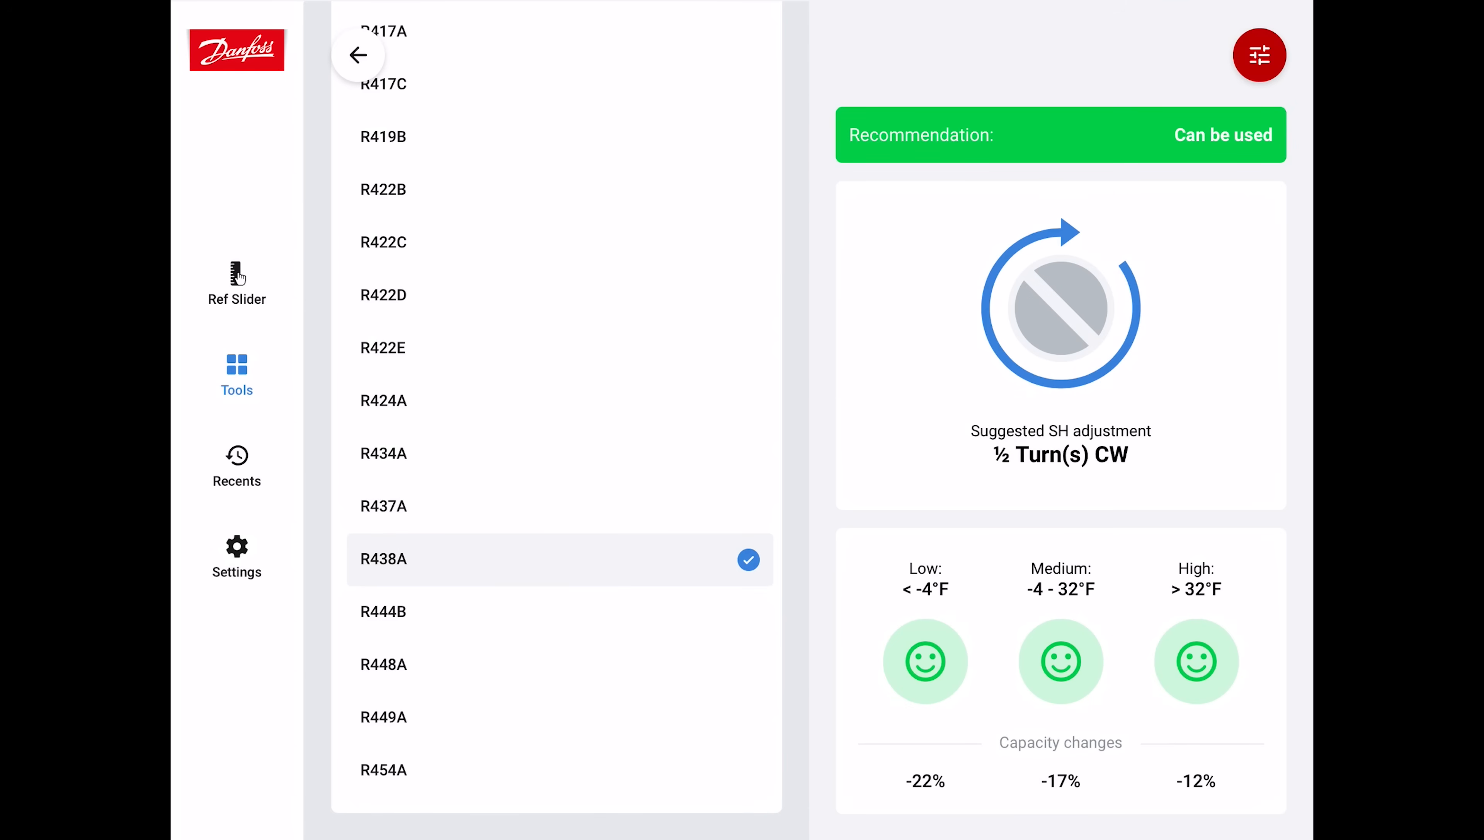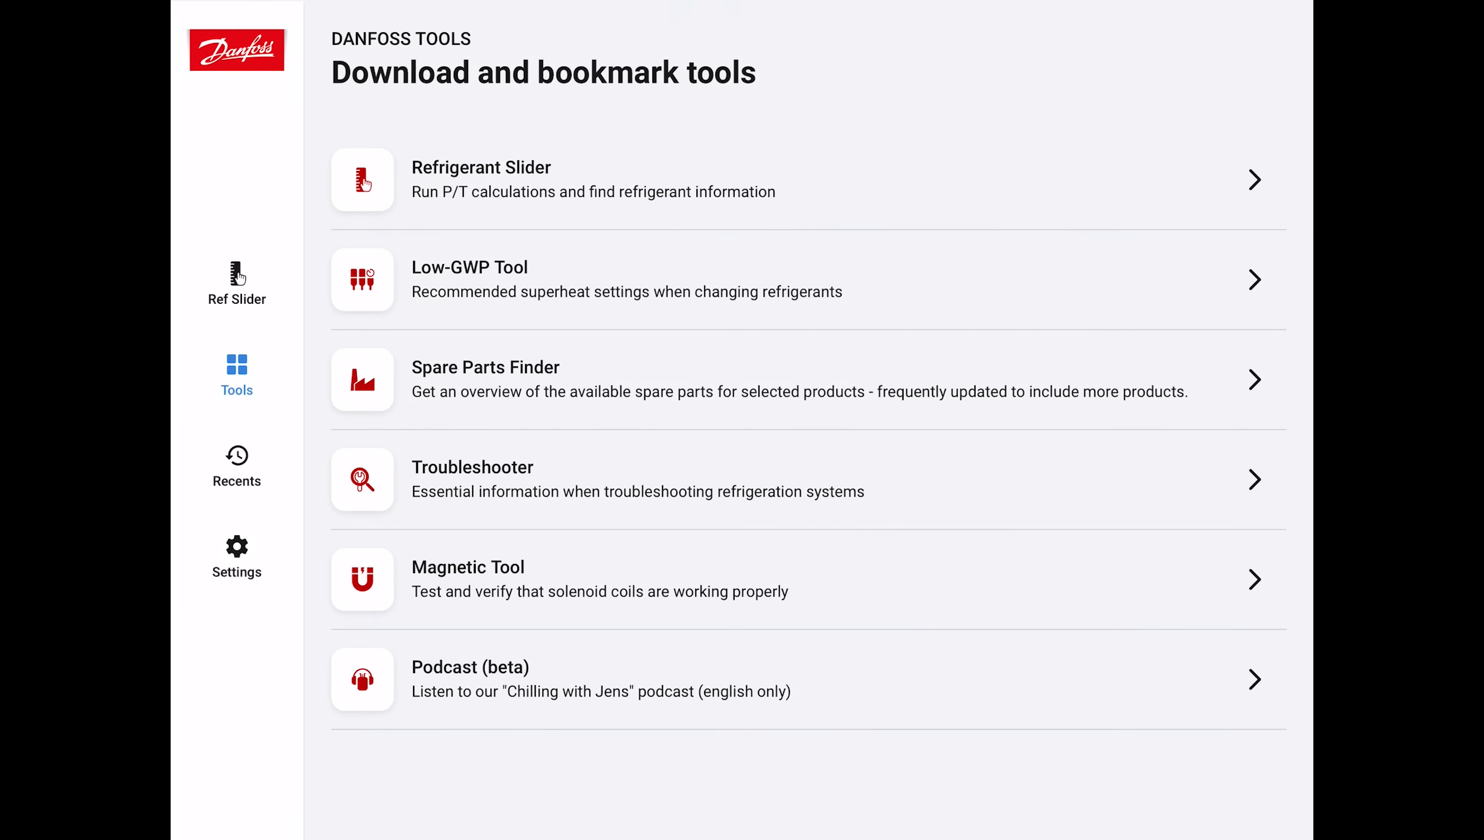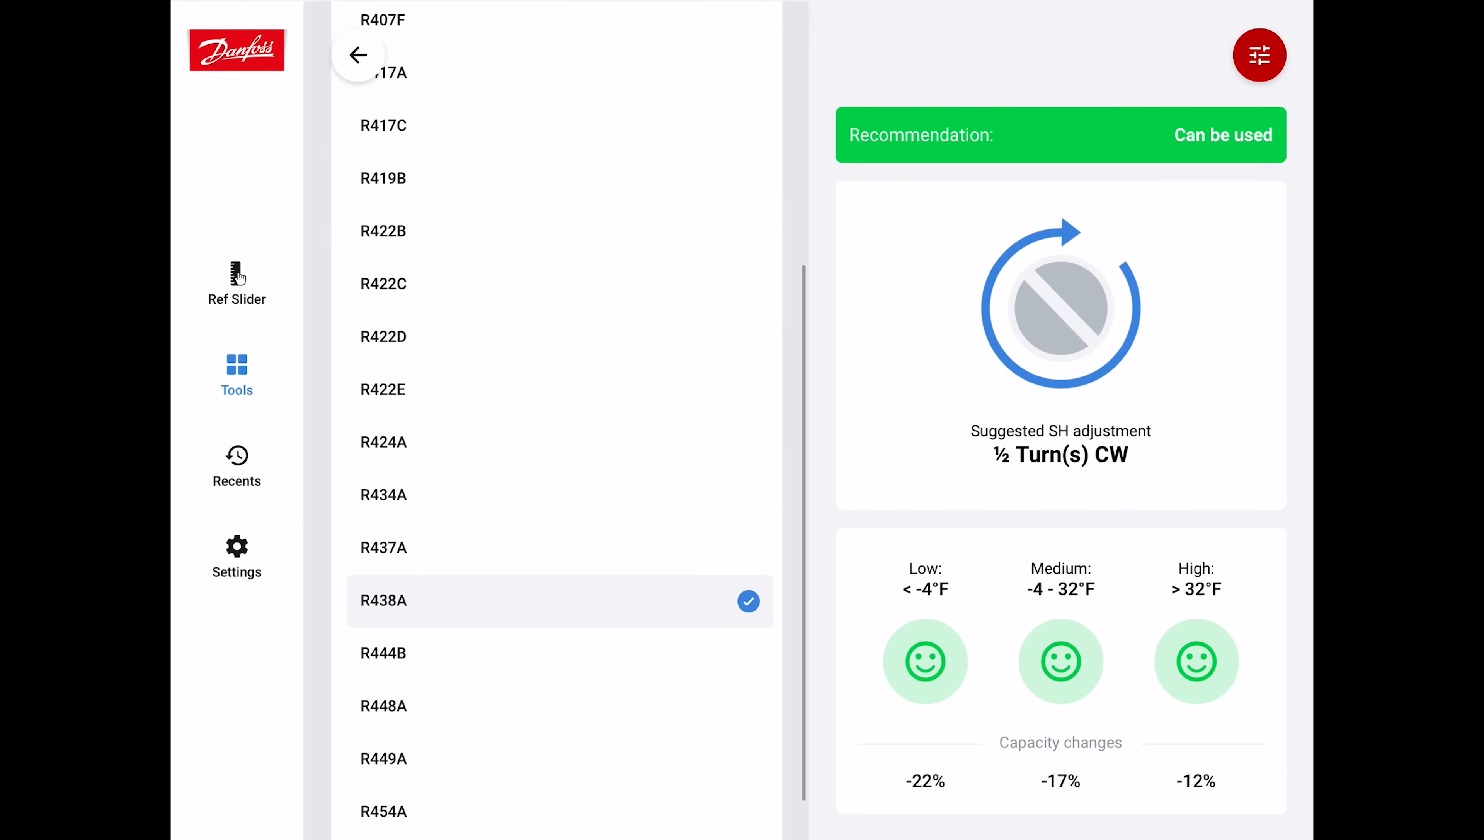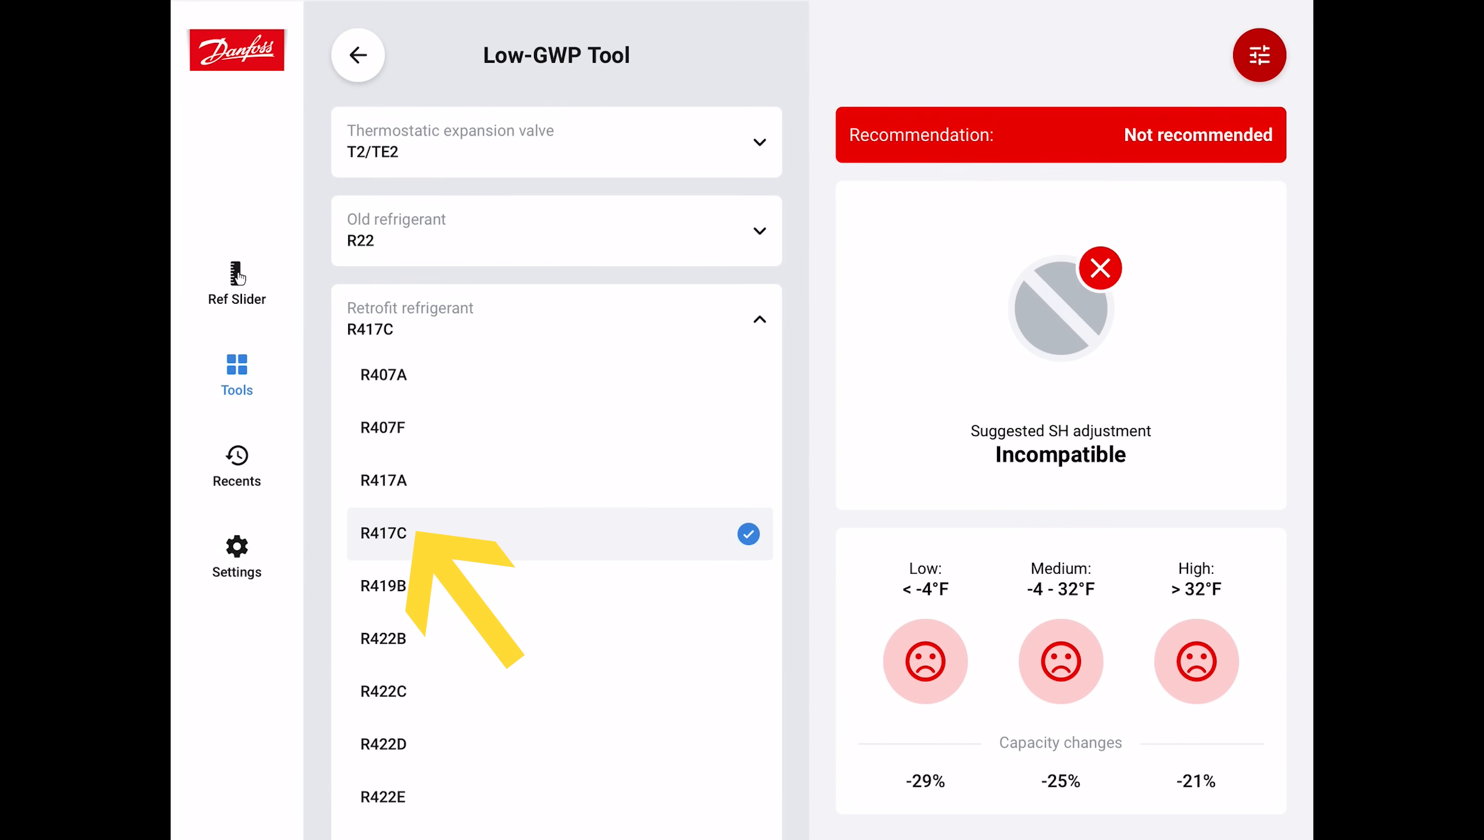This tool is also going to tell you whether it's a good idea to replace a refrigerant with another refrigerant such as R22. If we select a refrigerant such as R417C, you can see that's not recommended to be able to replace R22 with. It says you can't use it for a low pressure system, medium pressure system, or a high pressure system. The capacity changes are just way too high. It's just not going to work for that particular scenario.